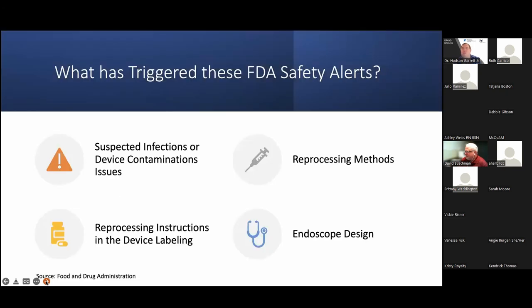So there's a couple of things that triggered these multiple FDA safety alerts. I'm going to give you a historical timeline here. First and foremost, there were actual infections reported. When we see contamination of the device that's genetically tied back to the isolate found in the patient, we know there's a match there, and our technology is so good now that we're able to do that.